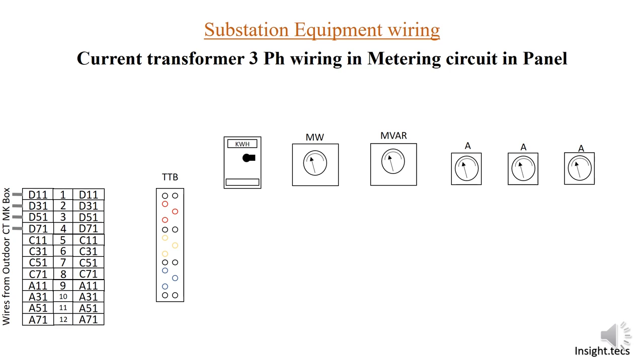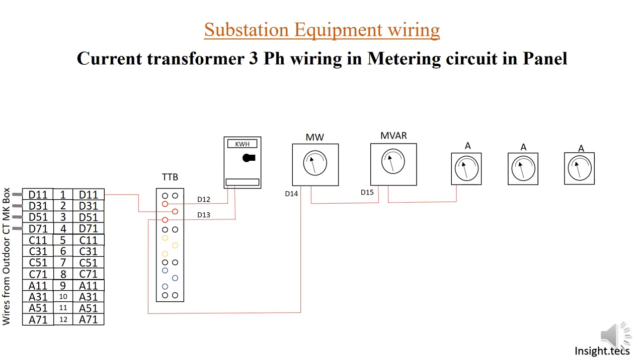Let us see how the connection is done for R-phase. From d11, one wire comes to the TTB. From the TTB, a connection is made to the energy meter — let us call that d12. Then there is another connection going from the energy meter back into the TTB, that is d13. Next, the megawatt meter is connected as d14, and d15 is the wire connecting the megawatt meter and the MVAR meter. Next, the ampere meter is connected and that wire is called d16.